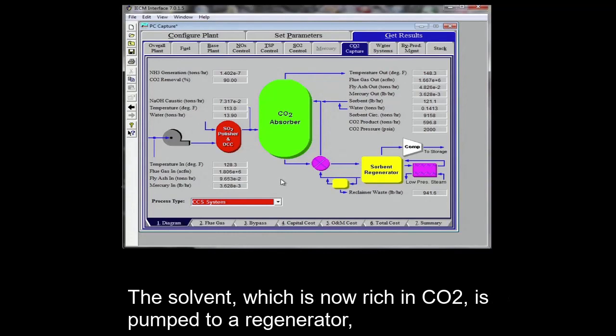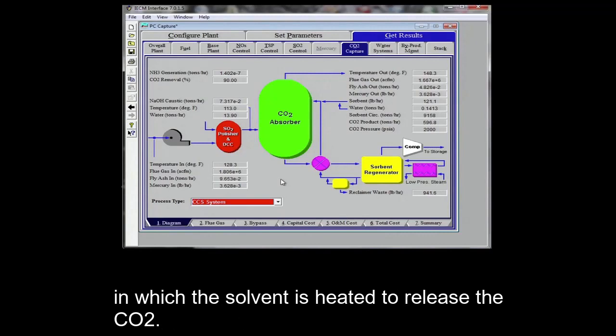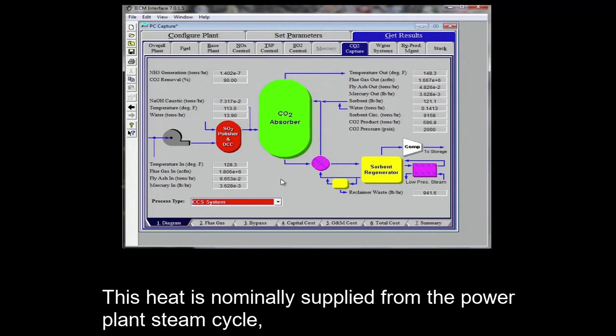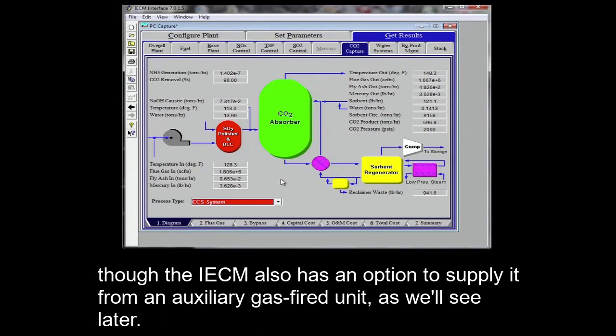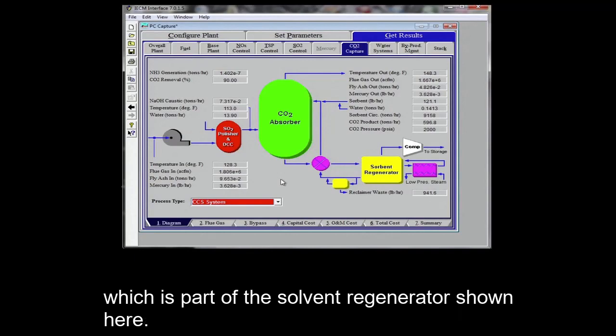The solvent, which is now rich in CO2, is pumped to a regenerator where the CO2 is released in a temperature swing process in which the solvent is heated to release the CO2. This heat is nominally supplied from the power plant steam cycle, though the IECM also has an option to supply it from an auxiliary gas-fired unit, as we'll see later. That heat is transferred to the solvent via a heat exchanger, also known as a reboiler, which is part of the solvent regenerator shown here.